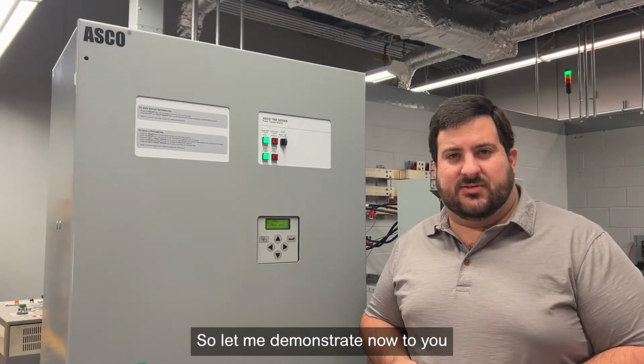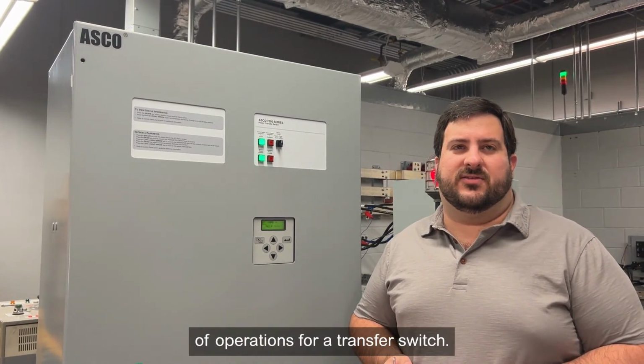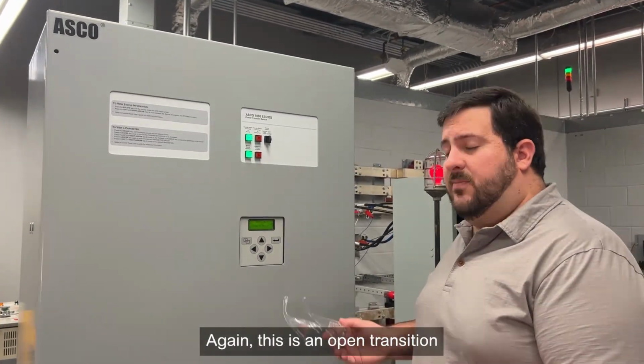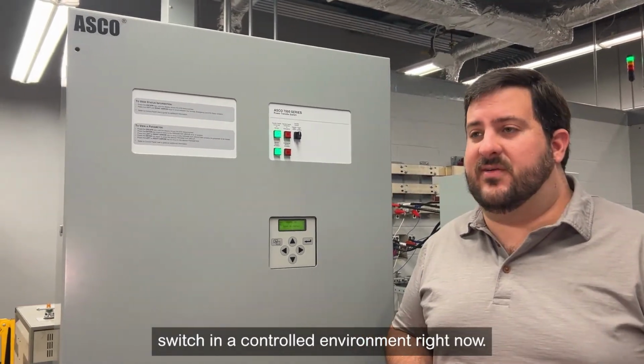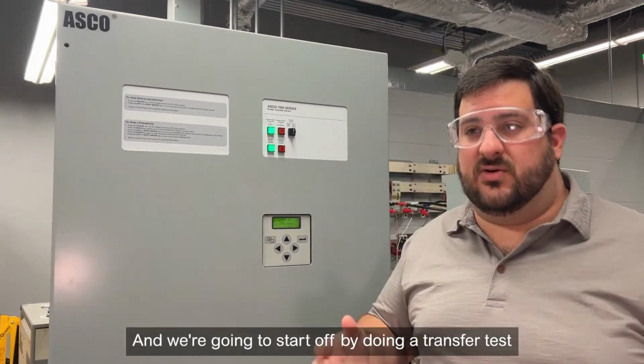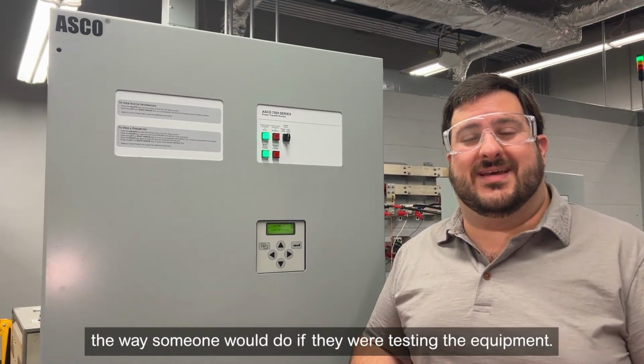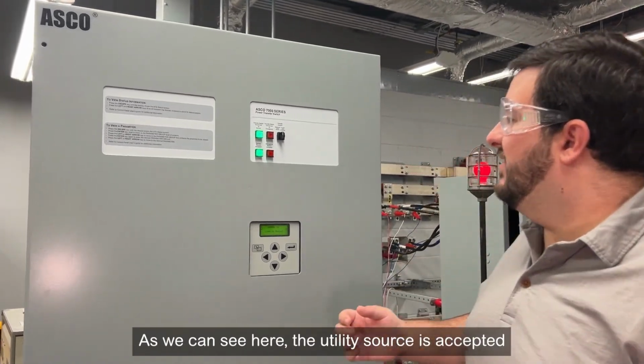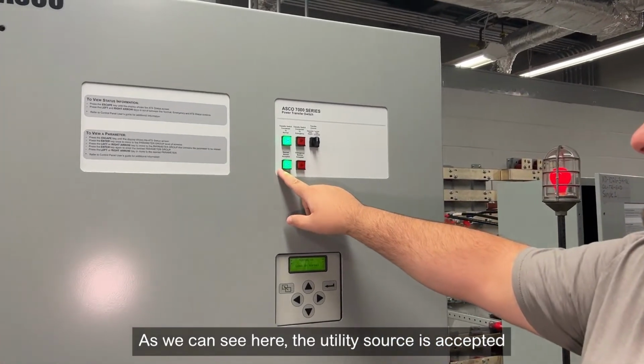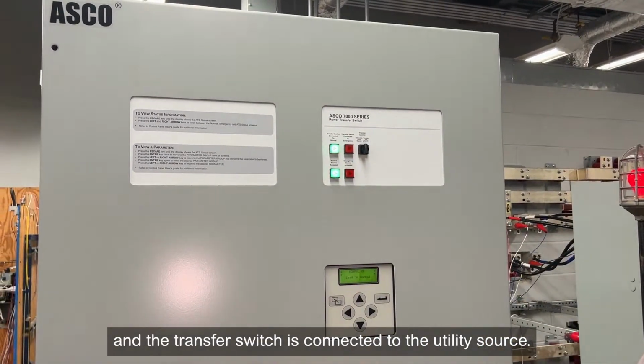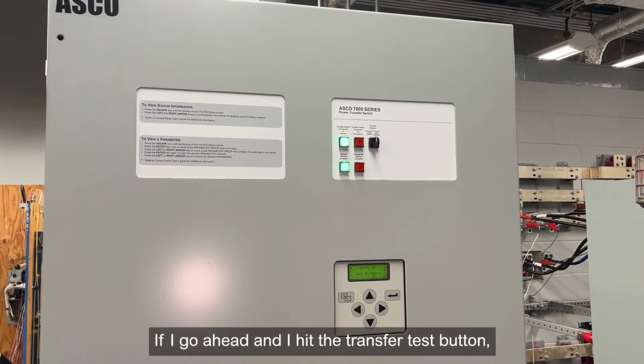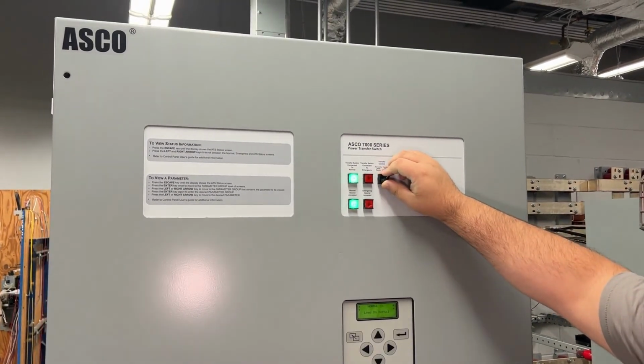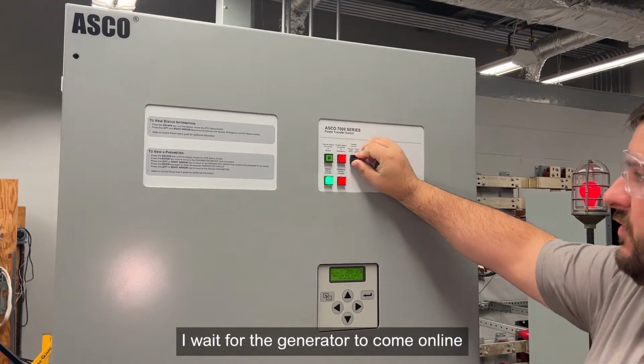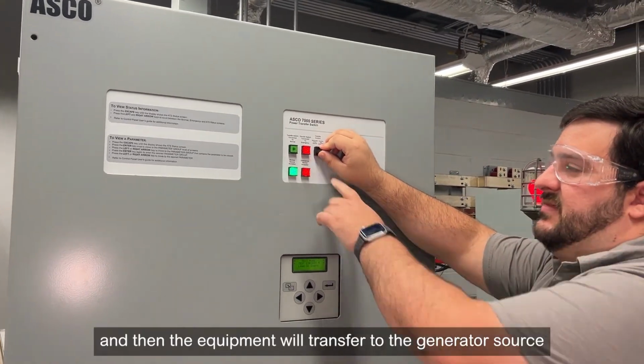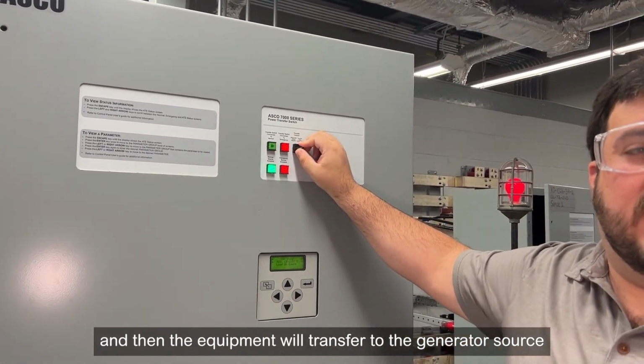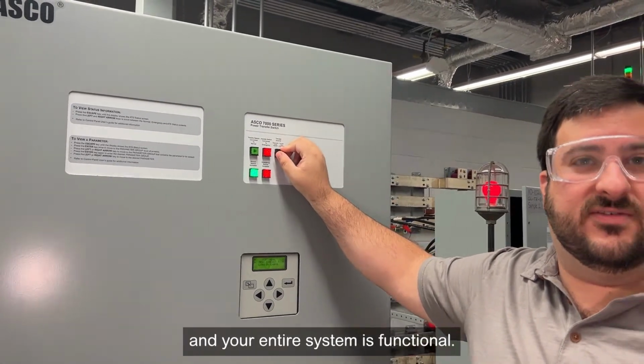So let me demonstrate now to you a couple of the most basic sequences of operations for a transfer switch. Again, this is an open transition switch in a controlled environment right now. And we're going to start off by doing a transfer test the way someone would do if they were testing the equipment. As we can see here, the utility source is accepted and the transfer switch is connected to the utility source. If I go ahead and hit the transfer test button, it will send an engine start signal, wait for the generator to come online, and then the equipment will transfer to the generator source, proving that the equipment and your entire system is functional.